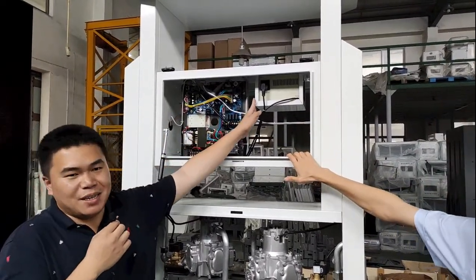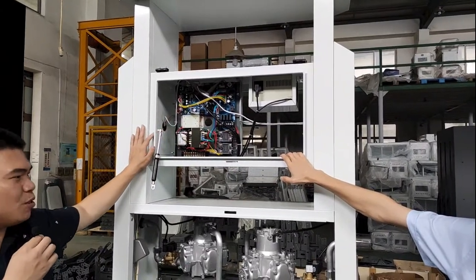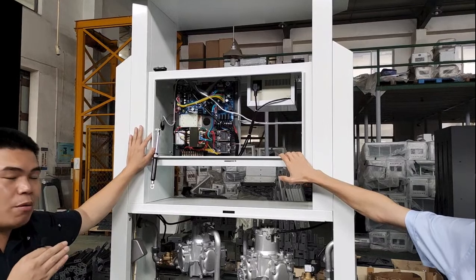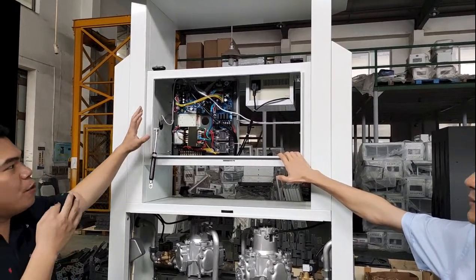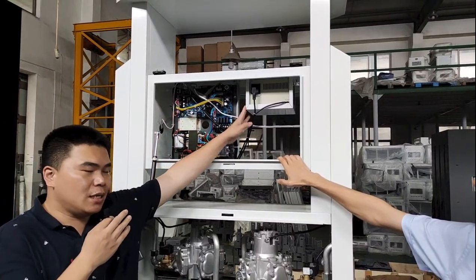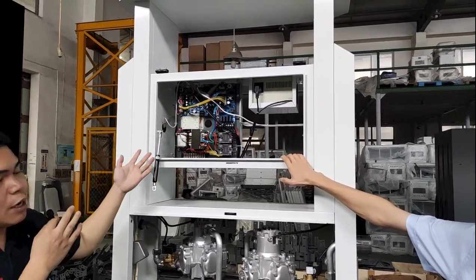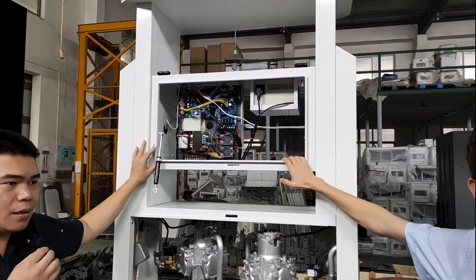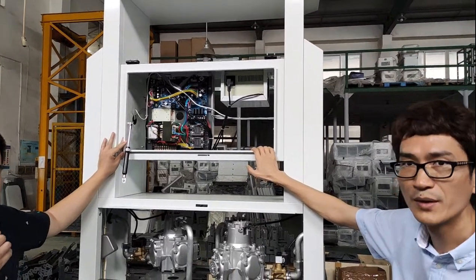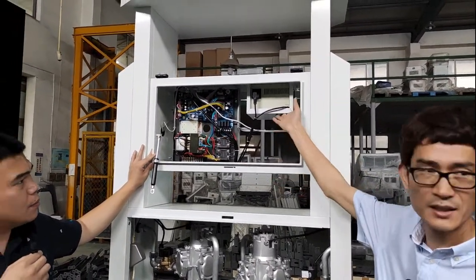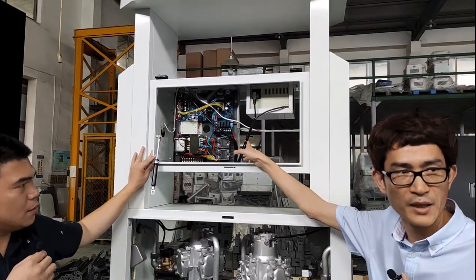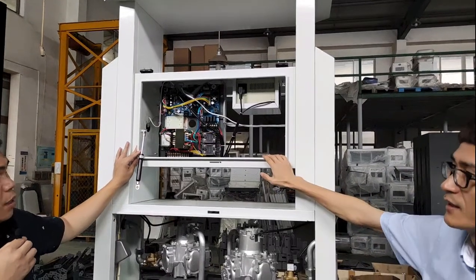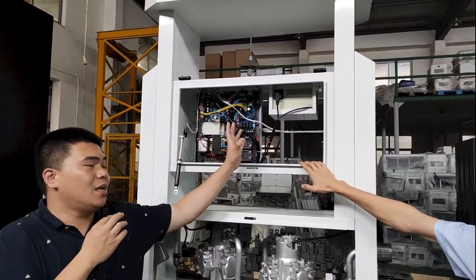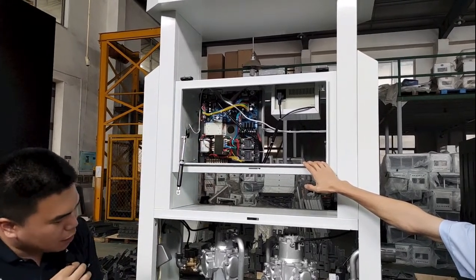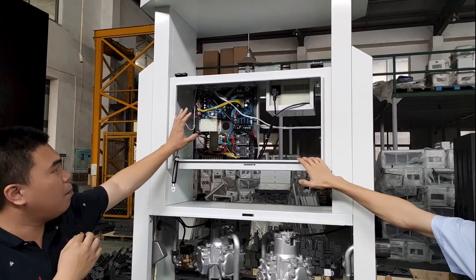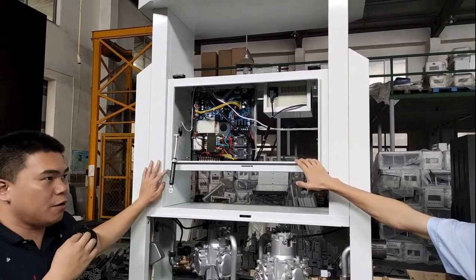What's this? Oh, this is a stabilizer. Our customers like that, because sometimes filling station power is not stable, so they install the stabilizer to protect the controller and make the power stable, so the controller can work for a long time. In some countries or regions the power is too high or too low, so we use the stabilizer to protect the controller and make it work perfectly. We can even install a bigger one for the whole fuel dispenser to protect the motors and main board controller, around 5 kVA.